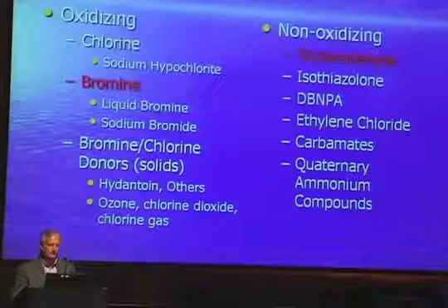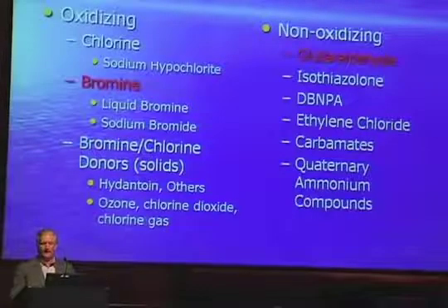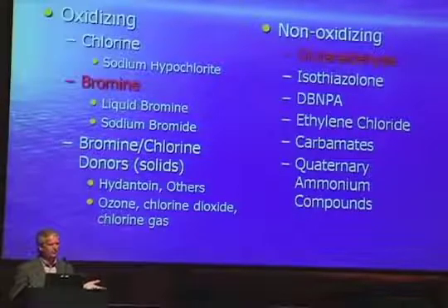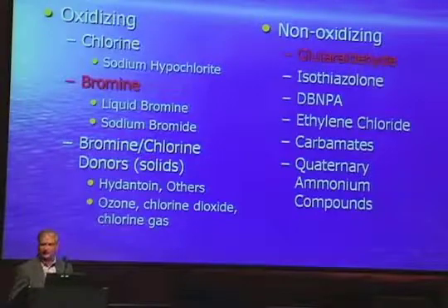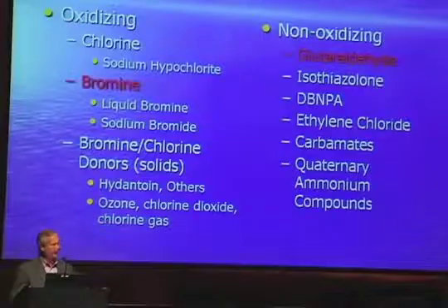Most of the best practices, including the Cooling Tower Institute guidelines, recommend both an oxidizer and a non-oxidizer, the oxidizer being your primary source of biocide. Why? One, it's fairly inexpensive. Two, it's a very, very rapid kill, and it's easy to apply.